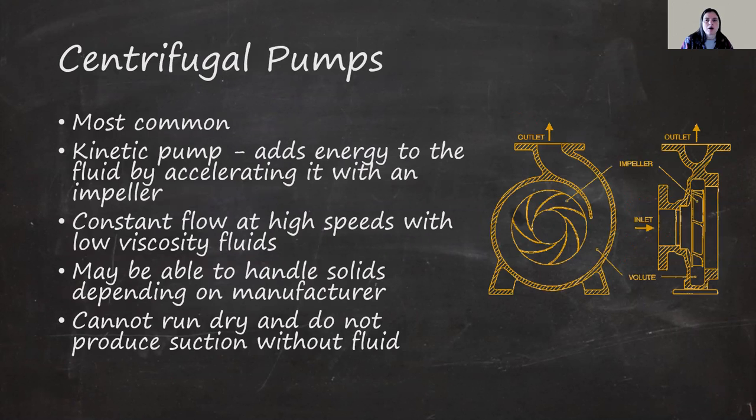The centrifugal pump is the most common pump. They're a type of kinetic pump which adds energy to the fluid being pumped by accelerating it with an impeller. They're good for transferring fluids at constant flow and high speeds however if pressure changes the efficiency and flow rate decrease. Because the impeller comes in contact with the fluid being pumped damage and excessive wear can be caused with high viscosity fluids. Certain centrifugal pumps can handle solids and abrasive slurries but these unique features will be based on the manufacturer's unique design. Centrifugal pumps cannot provide suction when dry and running them without a fluid will cause damage to the pump.